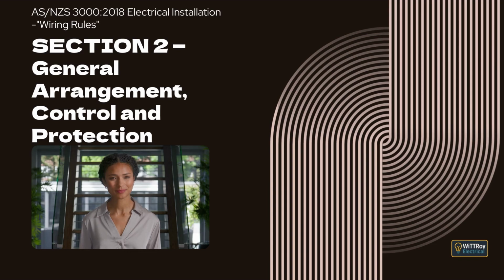Clause 2.8.2, Selection of protective device. The protective device used for undervoltage must suit the equipment it is protecting. It must follow the requirements and the relevant standards for starting motors and running electrical equipment. If switching the device back on could be dangerous, it must not automatically reclose. For example, if the supply drops out and comes back, we do not want a dangerous machine restarting by itself unless it is designed for safe automatic restart.